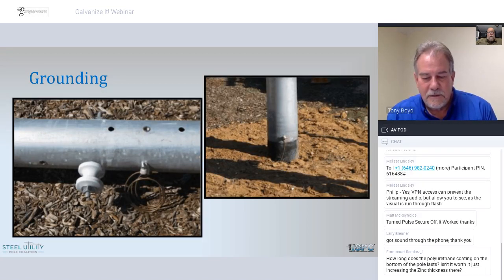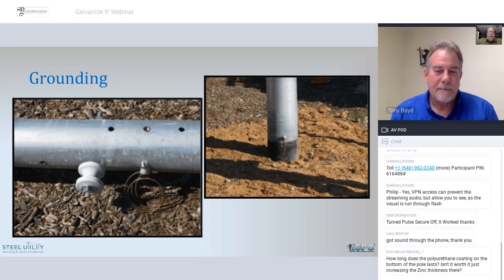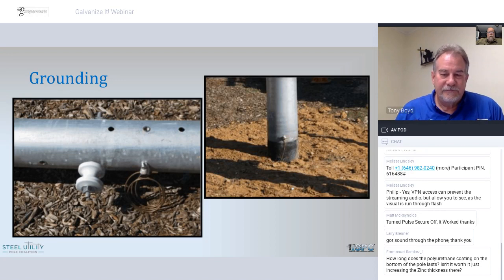There's one other reaction issue, and that's older gas line systems that had galvanic protection using those series DC currents or negative current in order to protect the steel pipe. Over the years, we've always had trouble with those old steel gas lines eating galvanized anchor rods. It'll actually create a penciling of the rod until it fails. So the same thing would happen to a steel pole.